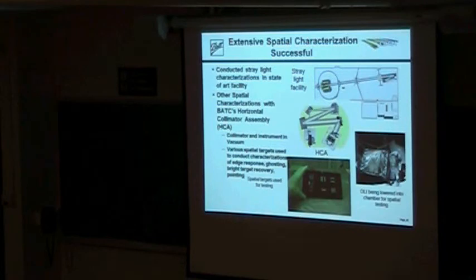In addition, we had to show that light from out of the scene was not getting into any given pixel to a certain degree, because that's a corruption of your actual signal in a given 30-meter ground sampling distance that you're actually trying to measure. So we have some very sophisticated facilities at Ball for measuring what's called stray and scattered light, which is a facility that is very darkened out, with a very well controlled field of view, and you project a very small point of light, very narrow field of view, and then you scan it around your instrument and you look for any ghosting or any light levels outside of where that light is. So we were able to measure our stray light in the out of field areas at better than 9 orders of magnitude down, which is very challenging to do.